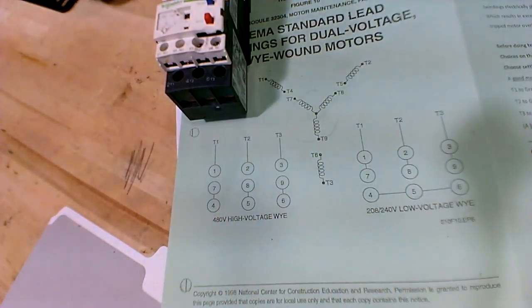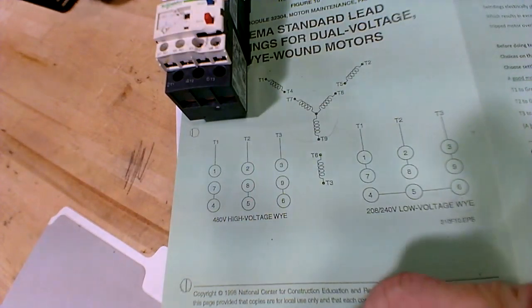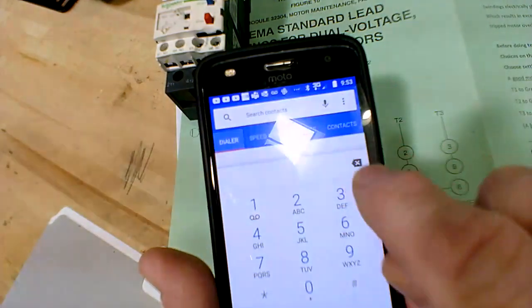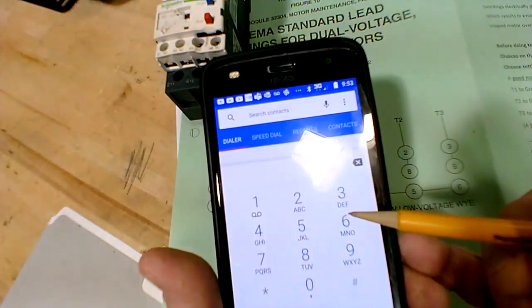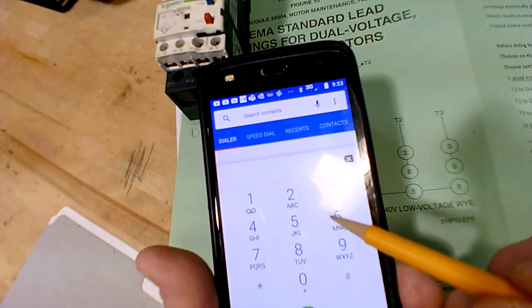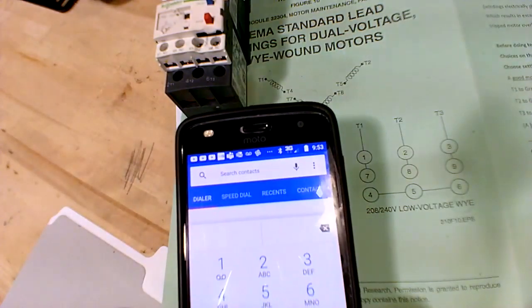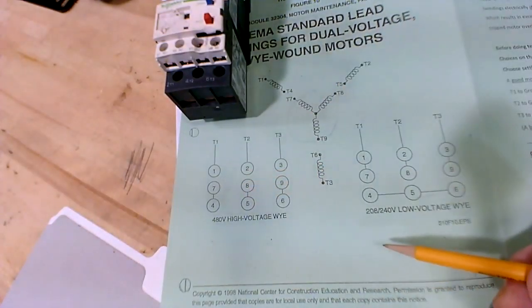Now this lines up with your dial pad on your phone. So I'll show you a little shortcut. If you're dealing with high voltage and it's a wye wound, here's how you can remember how to hook them up. Your dial pad actually tells you. So go to your phone and look, the incoming wires go to 1, 2, and 3 from the starter. And then you put a wire nut around 4 and 7, another wire nut on 5 and 8, another wire nut on 6 and 9, and this matches the dial pad. Okay, so that's a shortcut way to remember if it's high voltage 480 and it's a wye wound motor.